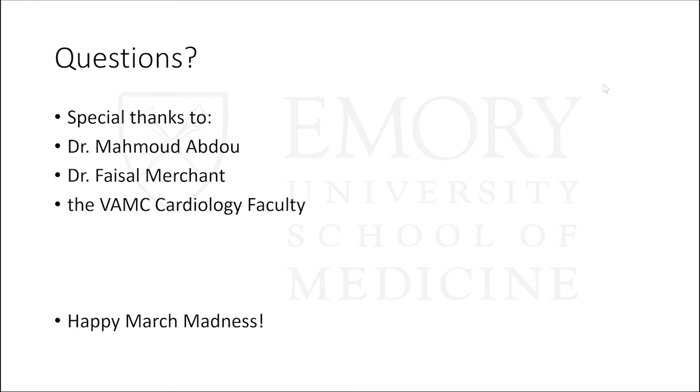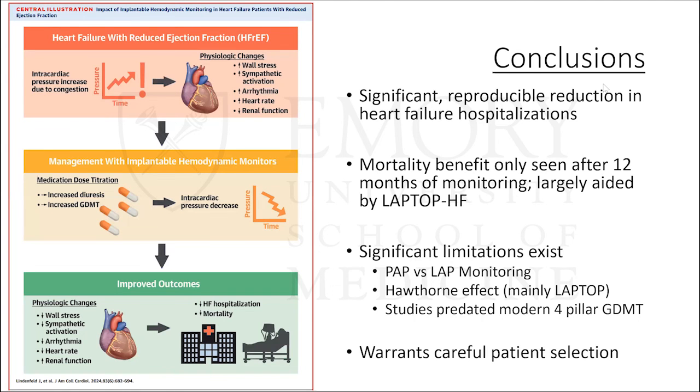The LAPTOP with the left atrial pressure monitor, the problem there was that there were too many complications in crossing the septum and having operators who may not have been used to doing that. So the things that matter with this are: does the monitoring system actually work? Can it be done safely? Will it work a long time? Will patients use it, which is an issue with CardioMEMS?